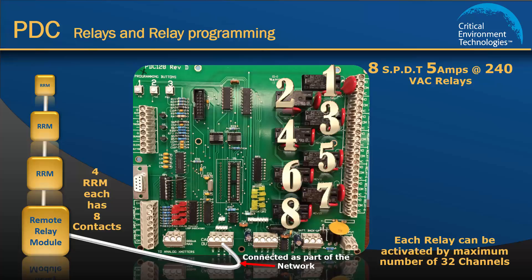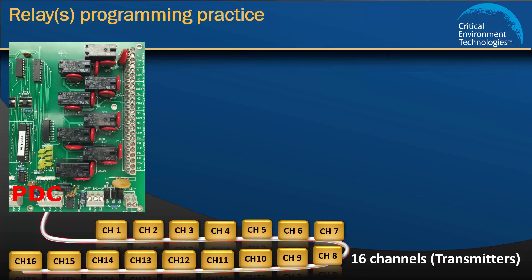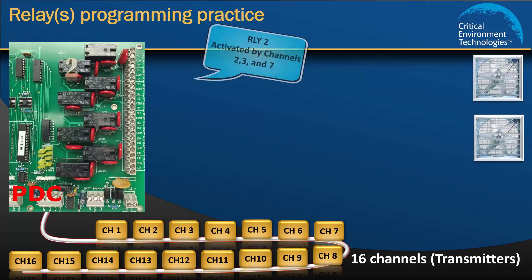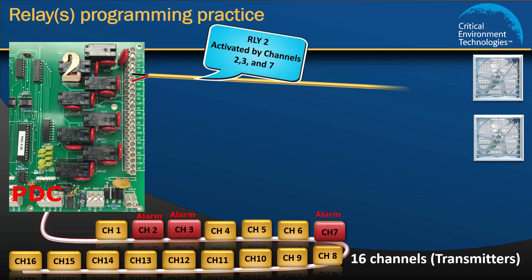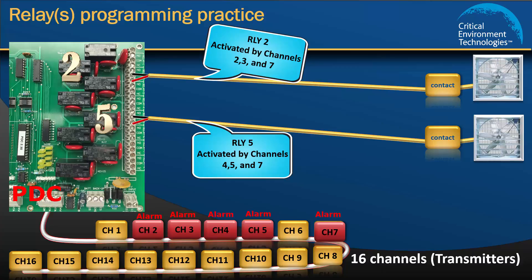A PDC uses a unique identifier, which we call a channel, that is assigned to each transmitter in the network so the PDC controller knows which unit it is communicating with. In this exercise there are 16 channels, or transmitters, and 2 fans. We are going to assign Relay 2 to be activated by channels 2, 3, and 7, and Relay 5 to be activated by channels 4, 5, and 7 for alarm conditions that send a signal to contacts that turn on ventilation fans.